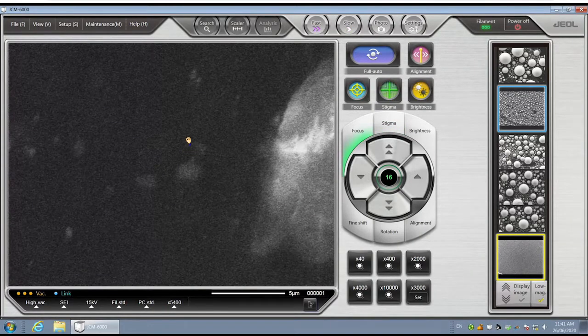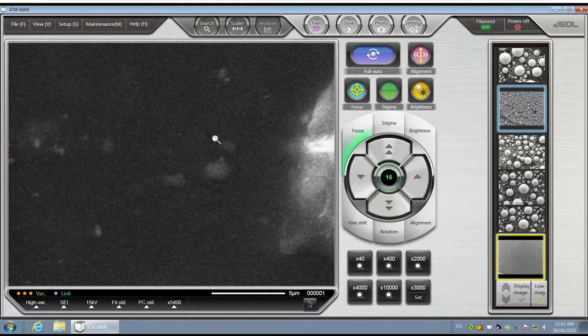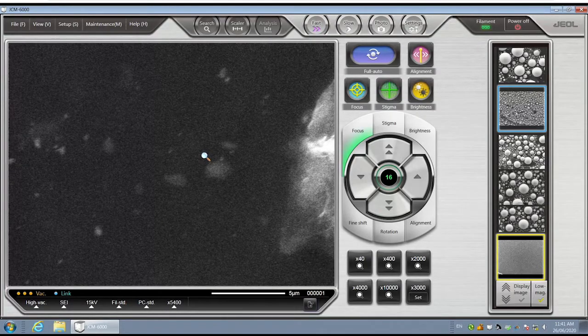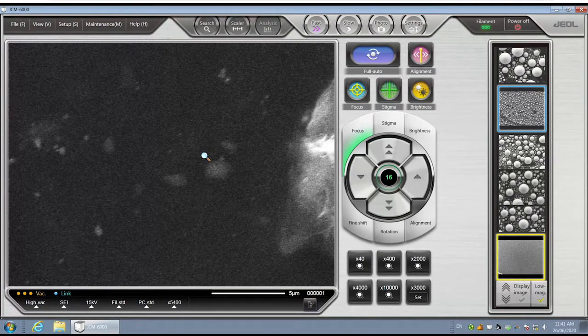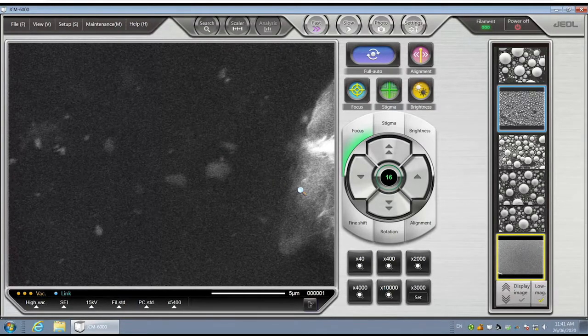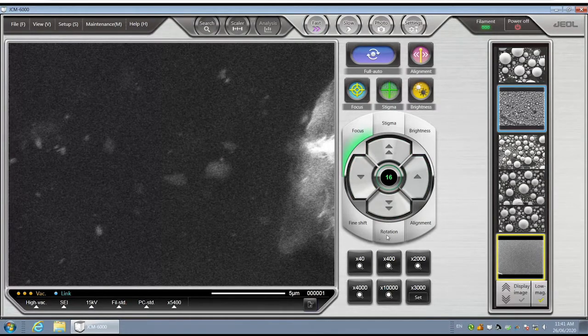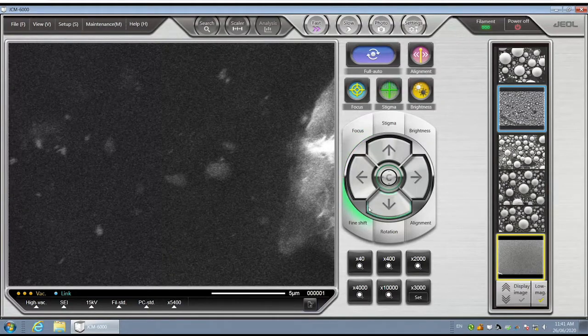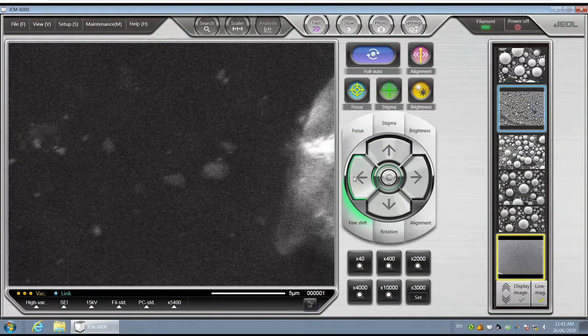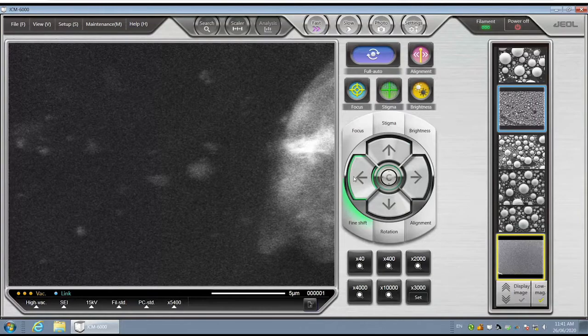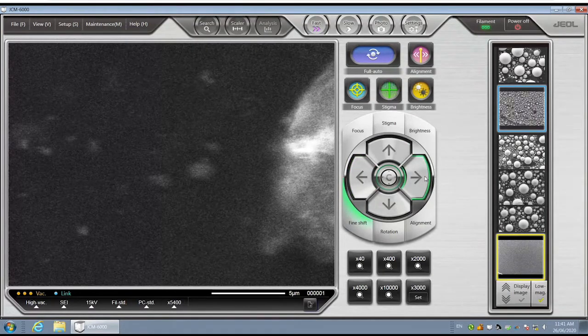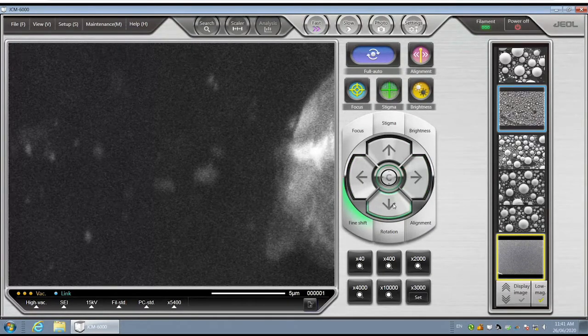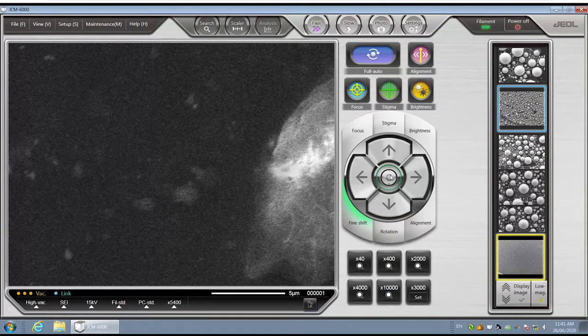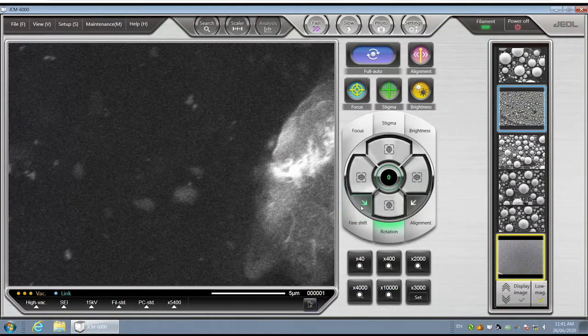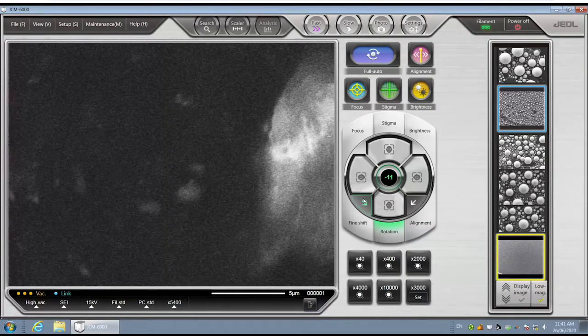Move to different areas or different samples using the X, Y, and rotation knobs. At high magnifications, moving the sample to get the right position may be hard. You can perform small beam shifts by left-clicking the image and dragging, or by selecting the Fine Shift button and clicking the corresponding directions, or select C to bring it back to center. You can also rotate the image by selecting the Rotation button and pressing the rotation options.